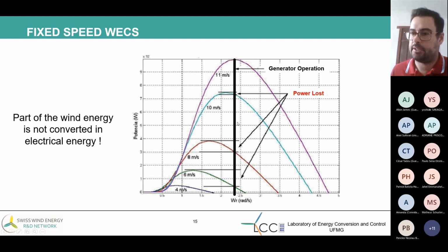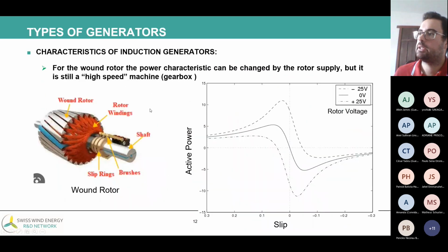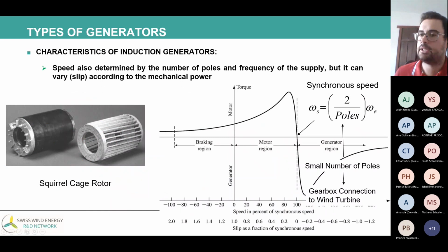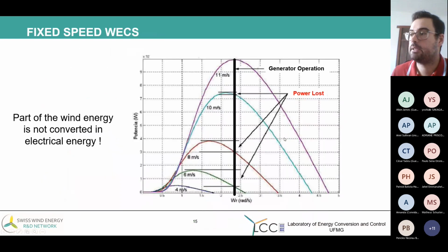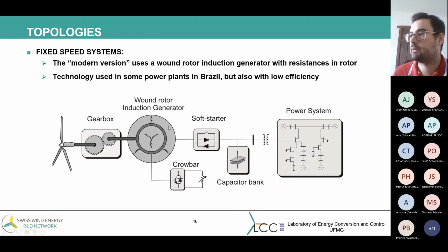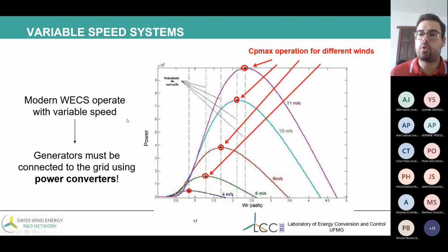The number of poles of the machine cannot be changed. This is the design of the generator. Each generator has its number of poles. So the only way to change the speed of the generator is to change the frequency of the supply. Of course, I cannot change the frequency of the grid, but I can use power converters to connect the generators to the grid.